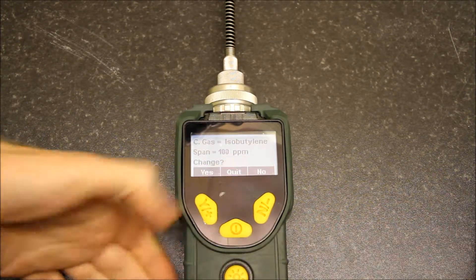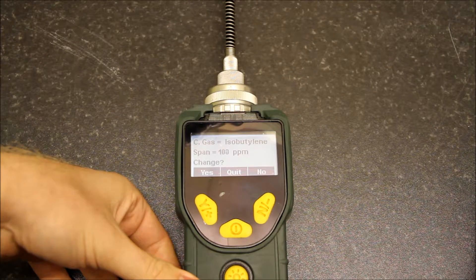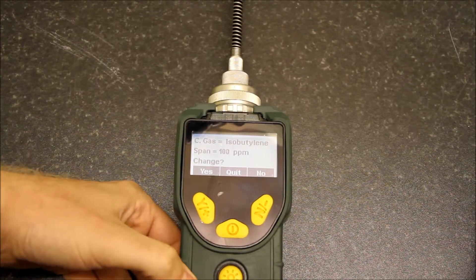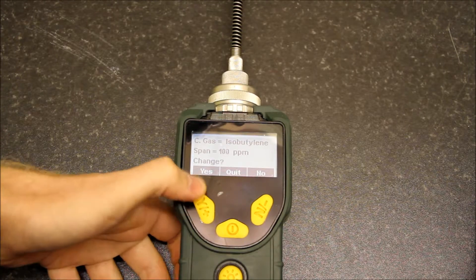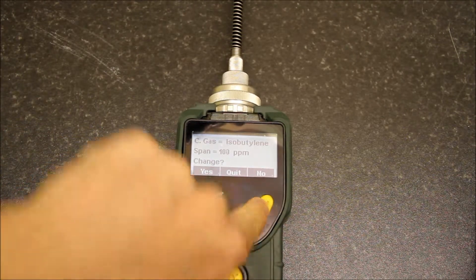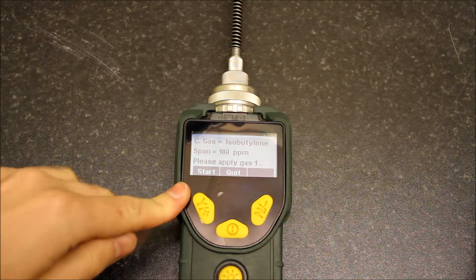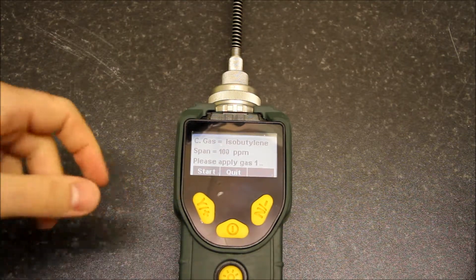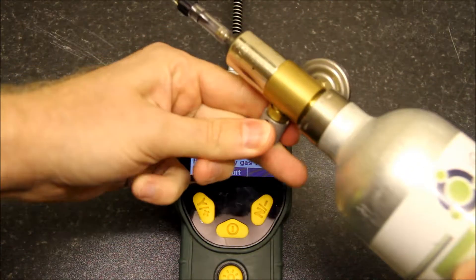We now press select. It's asking for what type of gas we're using and the span value. We are using 100 ppm isobutylene, and as such we don't need to change the value here. At this point we say no. Now it's asking for the gas to be applied, so I take my gas and turn it on fully.